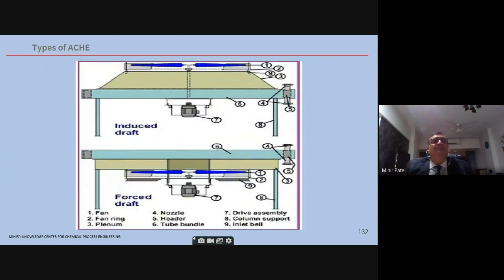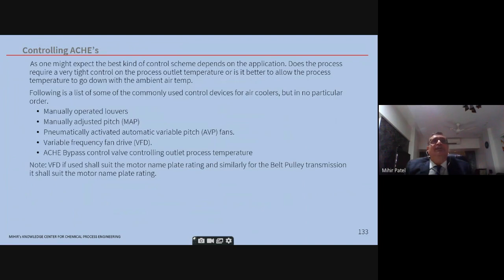Types of air-cooled exchangers: induced draft, where the fan is on the top and the tube bundle is below. Forced draft, where the fan is on the bottom and the tube bundle is on top. Now, controlling ACHEs. As you see in the middle, there are 5 methods: manually operated louvers, and manually adjustable pitch (MAP), where you have to stop the air-cooled exchanger in order to adjust the pitch. Then you have the pneumatically actuated automatic variable pitch (AVP) fans. Here you have a volume booster. Instrument air is used to adjust the pitch online.